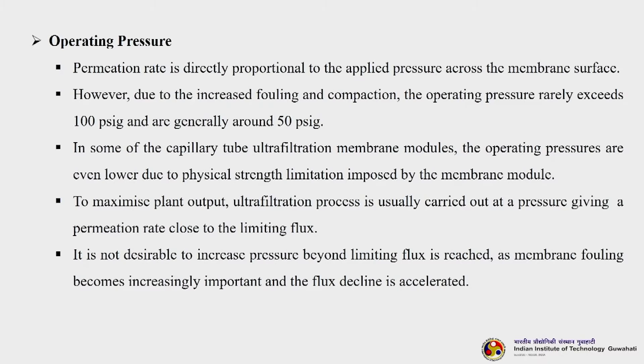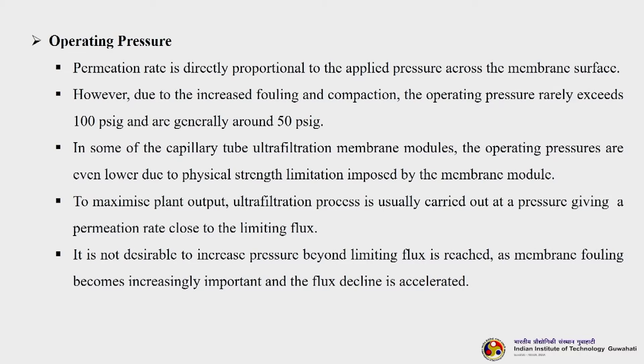The next parameter is operating pressure. Permeation rate is directly proportional to the applied pressure across the membrane surface. Since ultrafiltration is a pressure-driven process, the more you increase pressure, the more will be the permeation. However, due to increased fouling and compaction, the operating pressure rarely exceeds 100 psi and is generally around 50 psi. In capillary tube filtration modules, operating pressure is even lower due to physical strength limitations. The process is usually carried out at a pressure giving a permeation rate close to the limiting flux, beyond which membrane fouling becomes increasingly important and flux decline is accelerated.